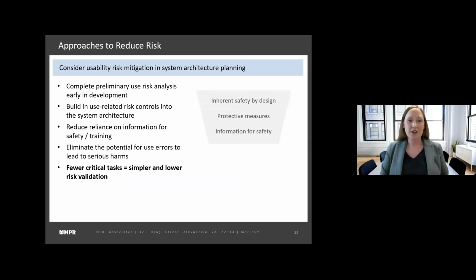The big one is to consider the usability risk mitigation early in system architecture planning. Complete your preliminary use risk analysis early in development and build in use-related risk controls into the system architecture or safety architecture of the system. Many of you are likely familiar with the hierarchy of risk control measures defined through our risk management process. Ideally, inherent safety by design first, then protective measures if we can't completely eliminate any risk, and then finally, least preferable is information for safety.